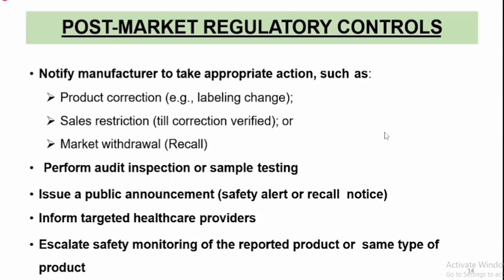So post-market surveillance comes with a few regulatory controls, and like our previous speaker has also mentioned, the medical device rules are related to this. As per the regulatory controls, it is mandatory to notify the manufacturers to take appropriate action after analyzing the data.